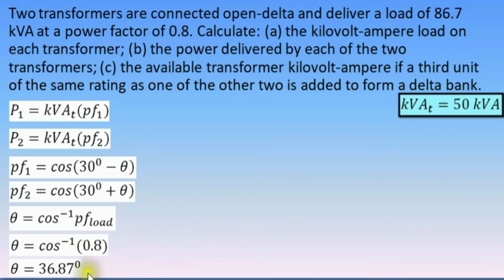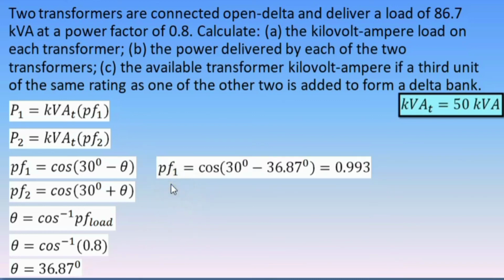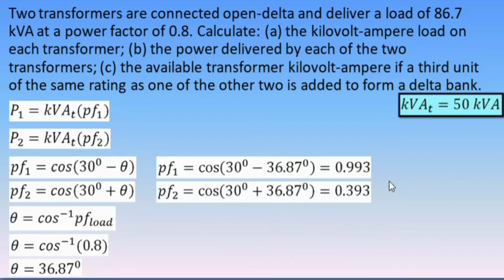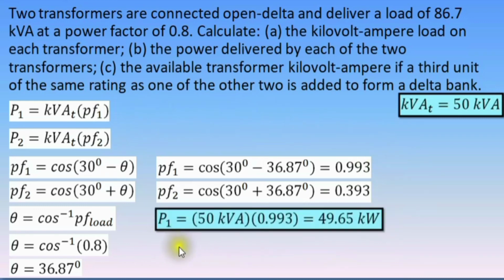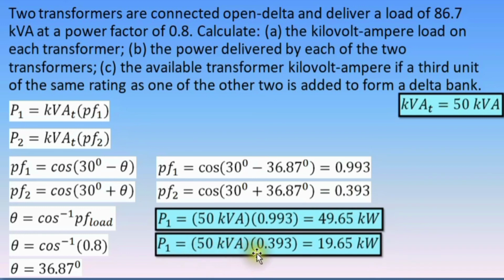Now that we have the power factor angle of the load, we can determine the power factor of each of the transformers. For transformer number 1, the power factor equals the cosine of the quantity 30 degrees minus 36.87 degrees. This is 0.993. And for transformer number 2, we have the cosine of the quantity 30 degrees plus 36.87 degrees. We have 0.393. Now we can determine the effective power delivered by each transformer. For transformer number 1, that is 50 kVA times 0.993, the answer is 49.65 kilowatts. For transformer number 2, 50 kVA times 0.393, the answer is 19.65 kilowatts.